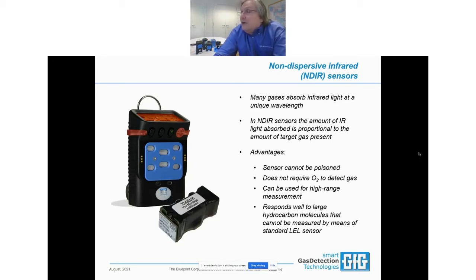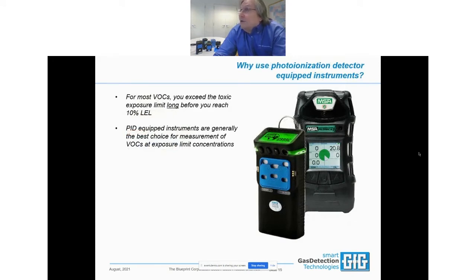What you have with the patented IR LEL sensor in the G888 and the G999 is an excellent quantified reading, and in the 888 and the 999, we can add additional sensors if we happen to be trying to measure something that is not detectable by an IR sensor, for instance, hydrogen. You can't detect hydrogen with one of those micro-miniaturized sensors. You can't detect it with the GfG IR sensor either, but you can detect it when we plug an electrochemical hydrogen sensor into the sensor as well. So we have a solution, we are safer, we are better, we are capable of giving you a quantified reading, and holy smoke, look at the size.